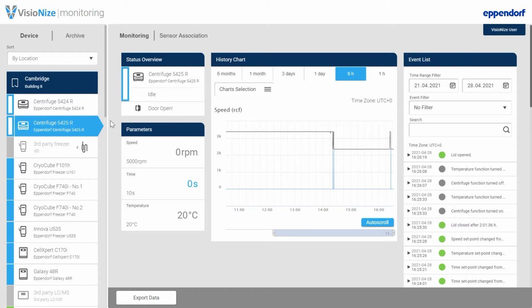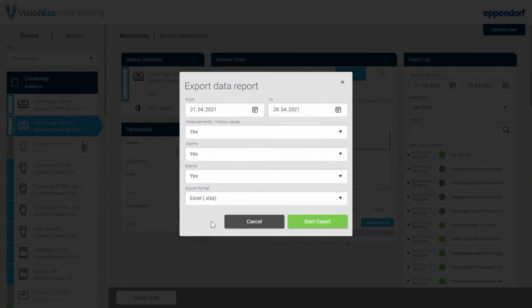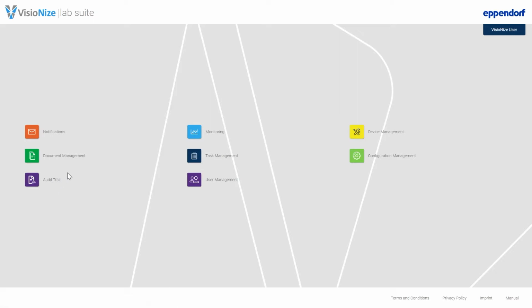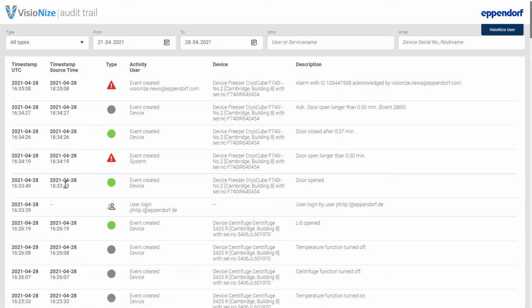You can check the current status of your device or receive a notification when a run is completed or when there is an error during a run. All kinds of historical setpoint changes are saved in the event log, and all parameter data is saved in a chart view. You can export all of that data to Excel and get an Excel export of all measurements, alarms, and events. The audit trail will document all device interactions, all alarm and errors, all maintenance activities that have been performed and who has performed these. And in case of an alarm notification that has been sent out, it's even documented who has acknowledged that alarm.